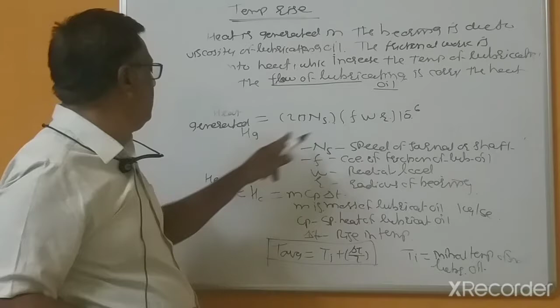Otherwise, what will happen if the heat carrying capacity is less as compared to the heat generation capacity? The temperature will rise more, and more heat will be present in the bearings. Because the machine and the shaft are continuously running, that heat has to be carried away, so these should be equal. If this is less, there is more heat, and the lubricating oil may lose its viscosity. So that's why this condition is very important.